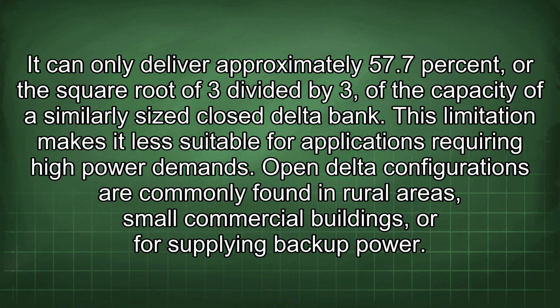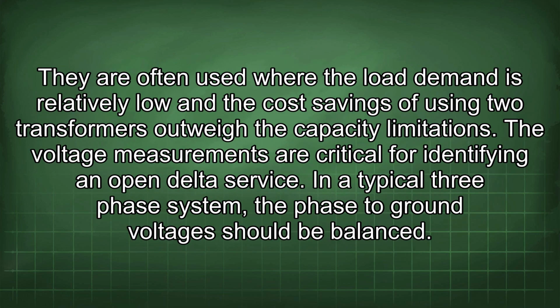Open delta configurations are commonly found in rural areas, small commercial buildings, or for supplying backup power. They are often used where the load demand is relatively low and the cost savings of using two transformers outweigh the capacity limitations. The voltage measurements are critical for identifying an open delta service.